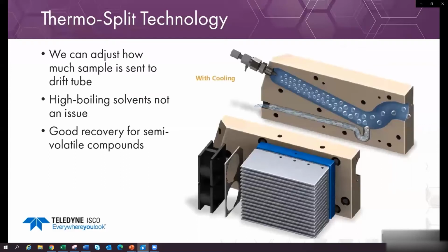For difficult-to-evaporate mobile phases or high flow rates, the walls are cooled. When the aerosol exiting the nebulizer encounters a cooled environment, it partially condenses into larger particles whose momentum carries them into the wall and down the drain. By making the walls cold, a portion of the vapor phase is diverted away from the evaporative zone.